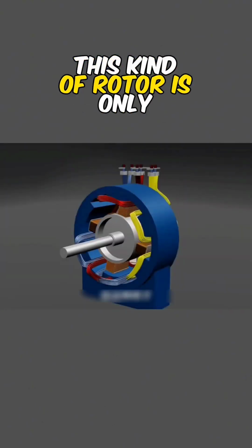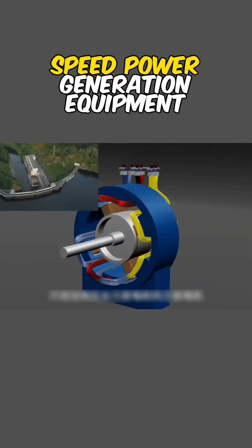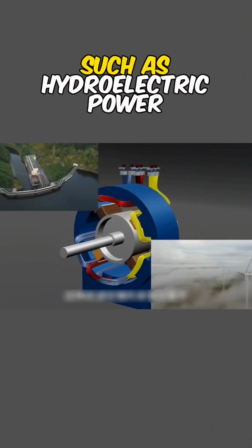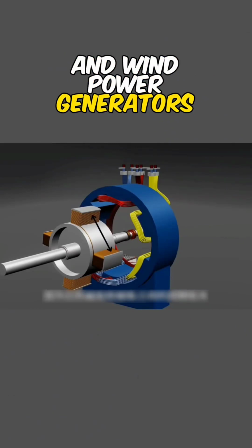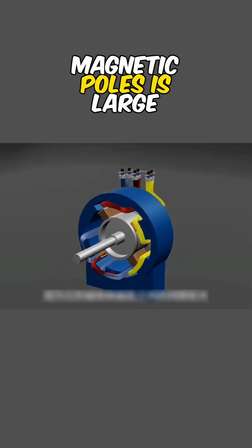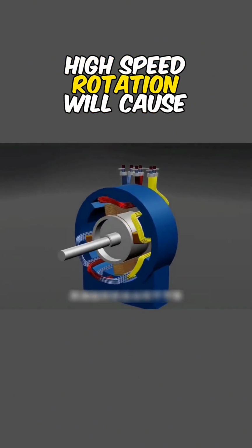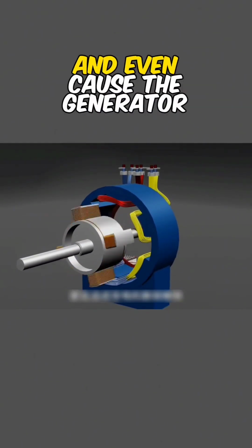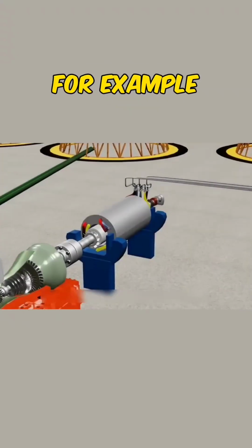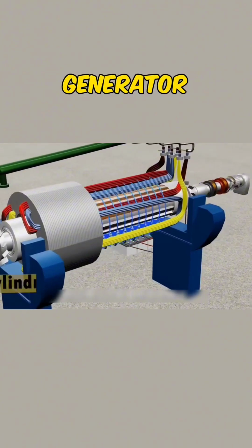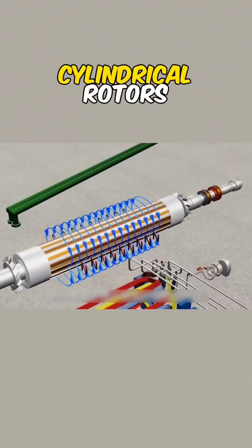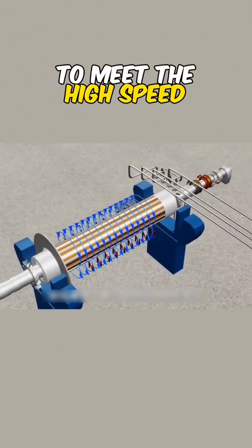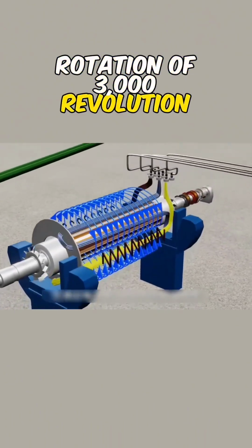However, this kind of rotor is only suitable for use in slow-speed power generation equipment, such as hydroelectric power generation and wind power generators. Because the gap between its magnetic poles is large, high-speed rotation will cause imbalance and even cause the generator to fall apart. For example, the rotor in a thermal generator is set into two magnetic cylindrical rotors to meet the high-speed rotation of 3,000 revolutions per minute.